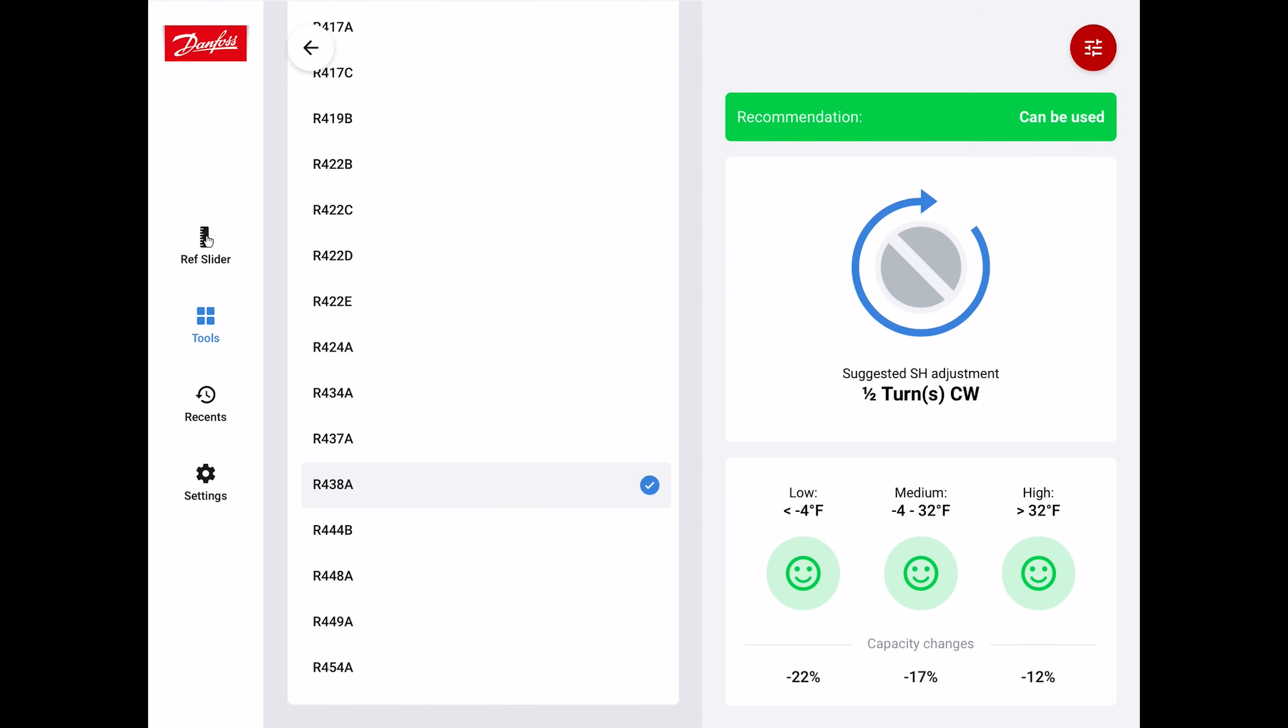The reason for that is maybe you have a slightly higher superheat when you have R438A in there compared to R22. If you had R22 in the system, maybe the superheat was 14 degrees. Now that you have R438A in there, you have a superheat of 18 degrees. If you adjust the TXV, if it has an adjustable TXV, you can make the system more efficient. For air conditioning systems, a lot of thermostatic expansion valves are non-adjustable.